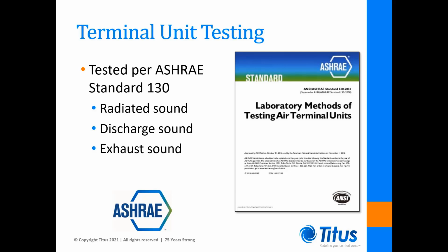Terminal units are sound tested in accordance with ASHRAE Standard 130. This standard details the test setups that must be used to determine sound power levels for radiated, discharge, and exhaust sound.